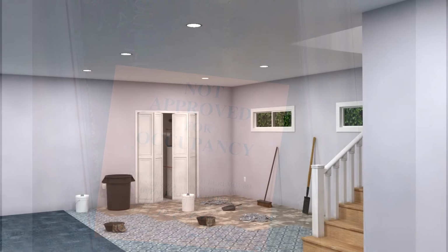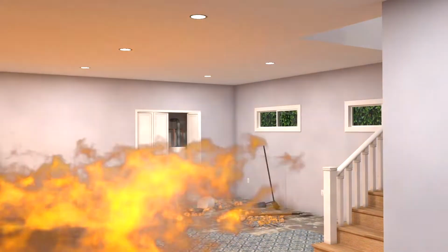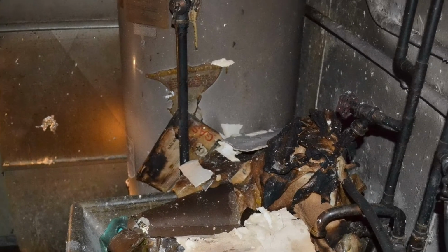And during the restoration in this townhome after this fire, there were several workers in the basement removing some floor coverings and using a solvent to loosen the glue. Unfortunately, the solvent produced flammable vapors that were ignited, injuring these workers. And during the litigation, the first target was the water heater. That's where they thought these flammable vapors were ignited.